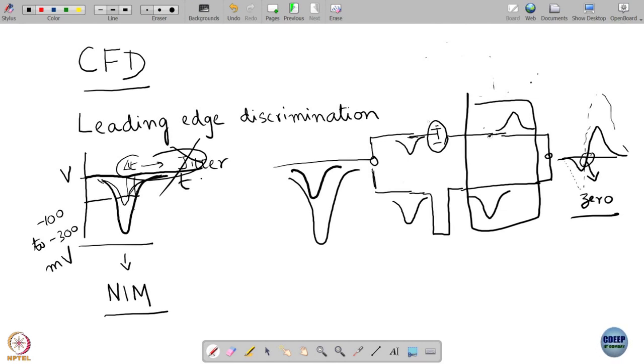So what we have learned is that we can do time-correlated single photon counting to record fluorescence decays in the range of hundreds of picoseconds to nanoseconds. We are not limited by the time response of the electronics because we are not trying to measure the time directly — we are measuring ΔT. To measure ΔT with precision and without timing jitter, it is important to use constant fraction discrimination rather than leading edge discrimination. Once we do that, we can obtain a clean decay in the desired time scale.